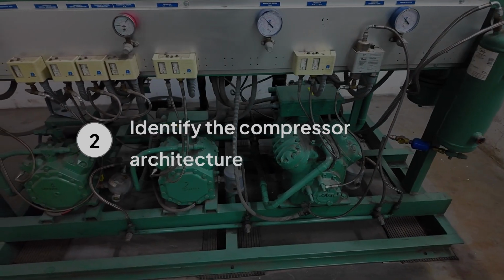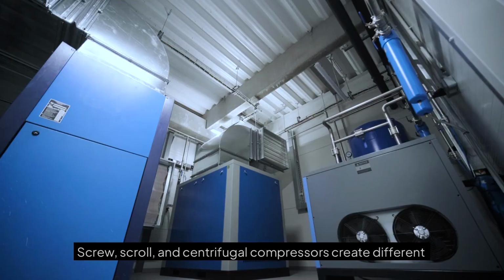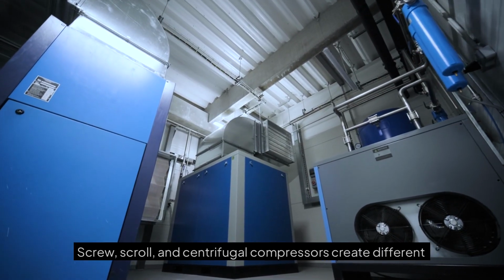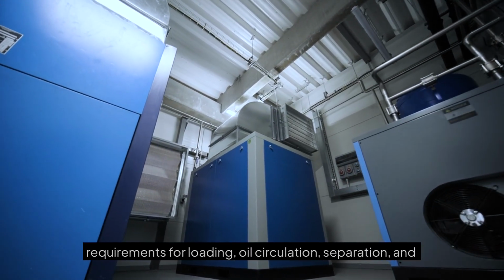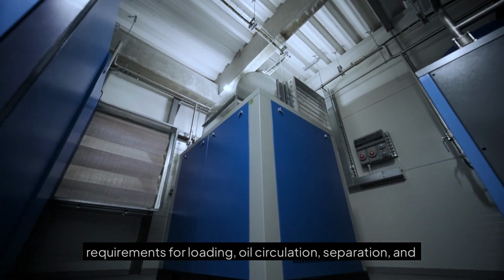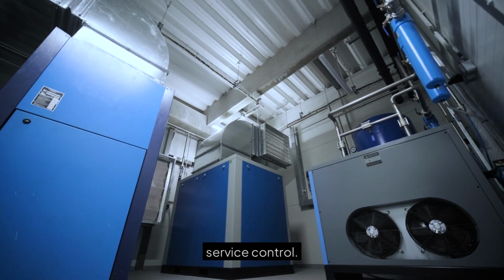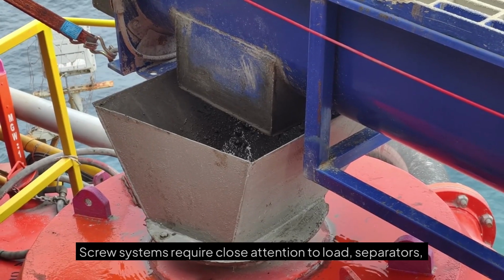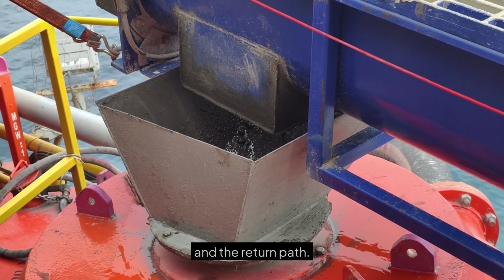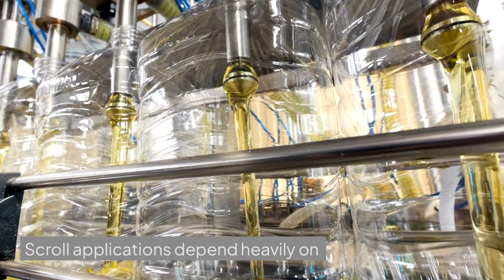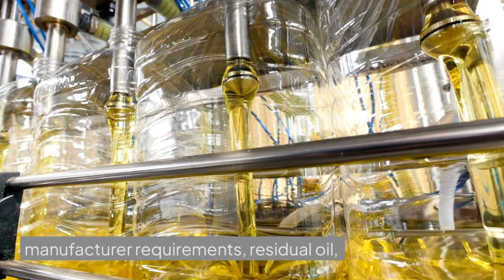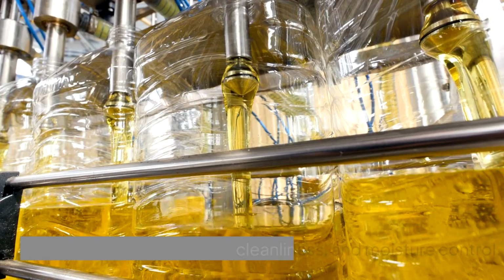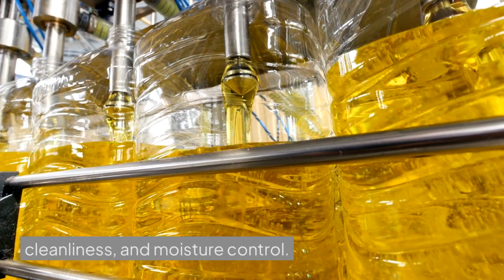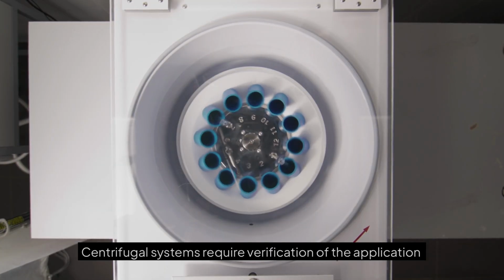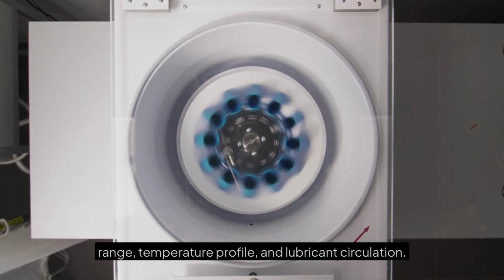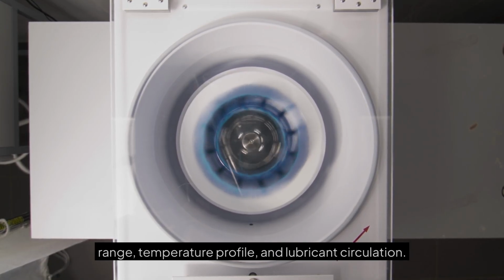Second, identify the compressor architecture. Screw, scroll, and centrifugal compressors create different requirements for loading, oil circulation, separation, and service control. Screw systems require close attention to load, separators, and the return path. Scroll applications depend heavily on manufacturer requirements, residual oil, cleanliness, and moisture control. Centrifugal systems require verification of the application range, temperature profile, and lubricant circulation.